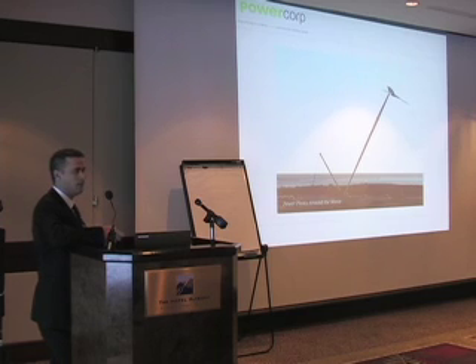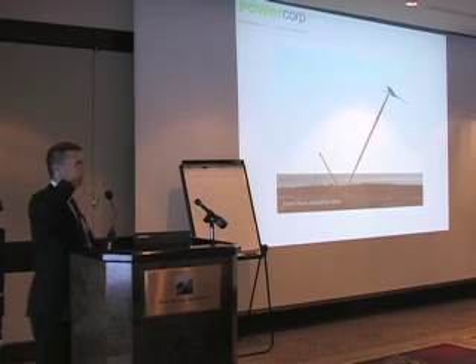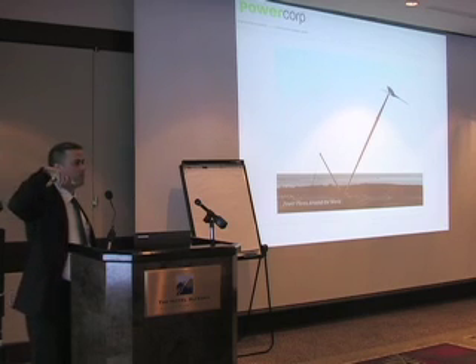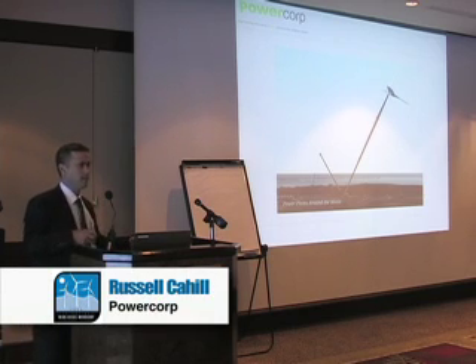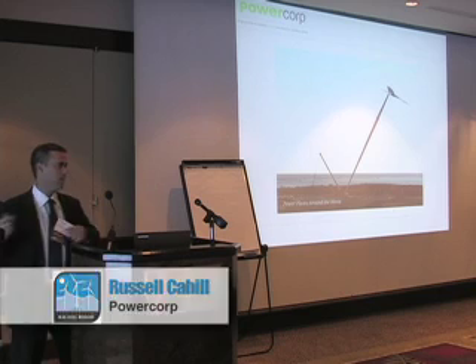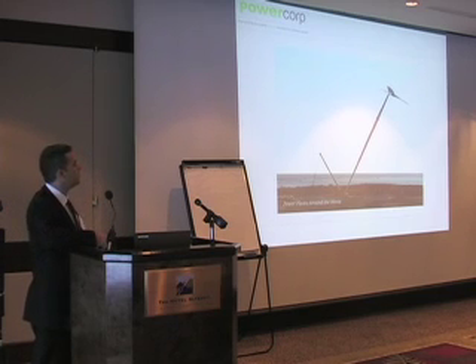We've even worked with these machines - I've got a couple of pictures of them. They're a French machine, made in France, we put them up in Australia. That wasn't the problem - they're an induction machine, and I believe there's induction machines up here, where given enough wind, the machine will put in up to 150% of its rated output for a little while until it pitches its blades. On top of that, it's also got a gearbox, so halfway through the power range it just turns itself off, changes gears and keeps going, which is pretty cool - except if you're the diesel power station that suddenly has to pick up all the energy while it changes gears and then goes back on. So they are pretty wild machines to work with.